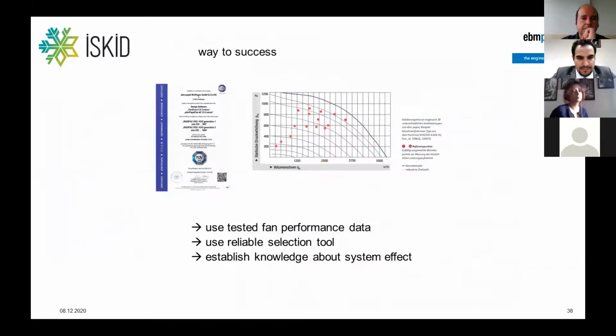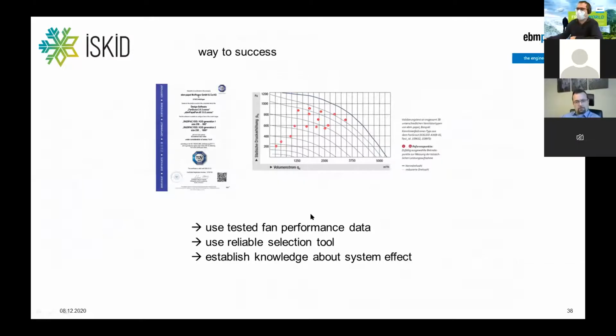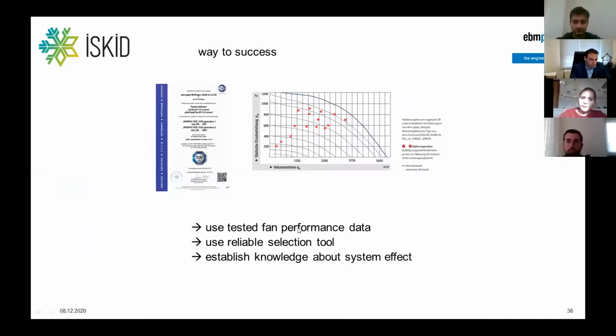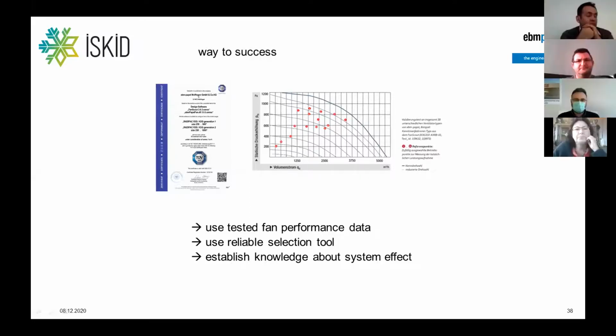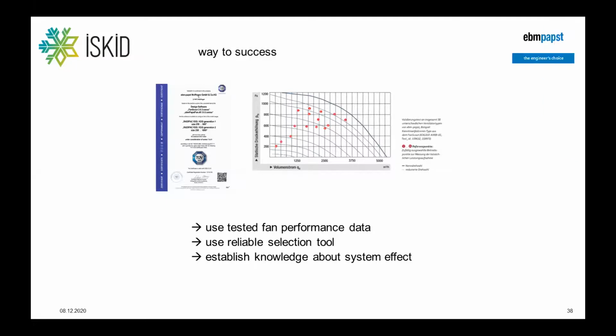So the way to do the fan dimensioning in a proper way is to use tested fan performance data if available. And the selection tool is also one part. Does the selection tool really consider the part load behavior and all the components that make up the fan? Just the fan curve does not really give you good information. And then knowledge about system effect. This is very critical, as you have seen before. Fan manufacturers can help on the fan side with things that are very close to the fan, so the dimension, the distance to the walls, etc. We have a certain knowledge of this. But all the other things that happen in an air handling unit, like the position of the discharge, dimensioning, etc., have to be handled on the AHU manufacturer side.